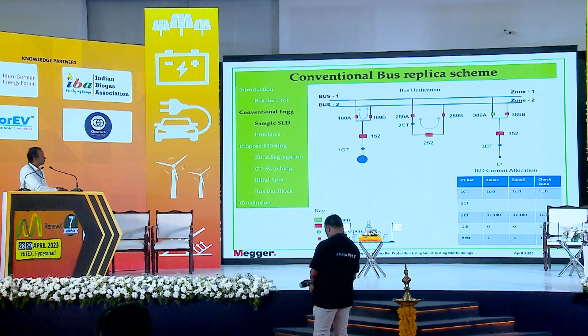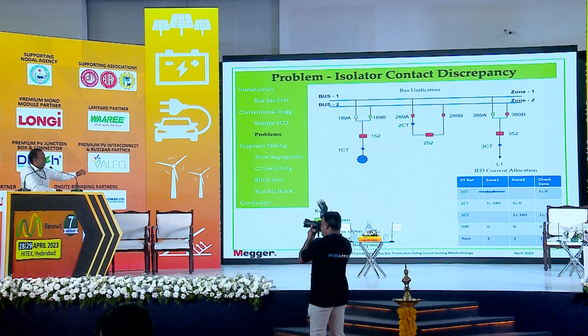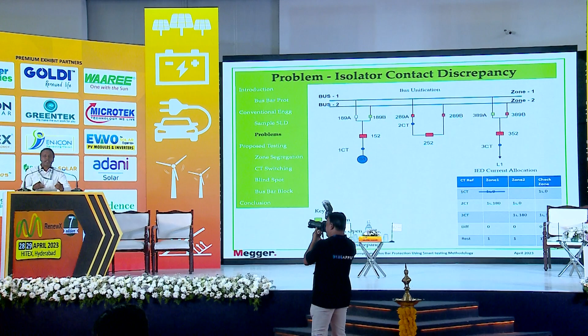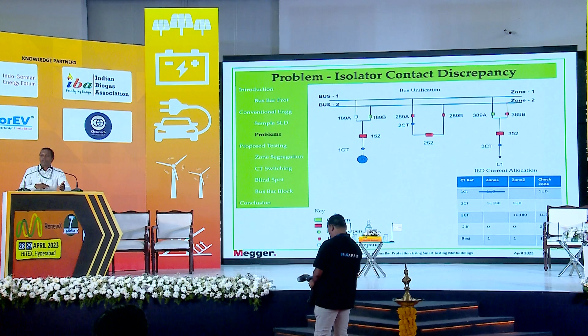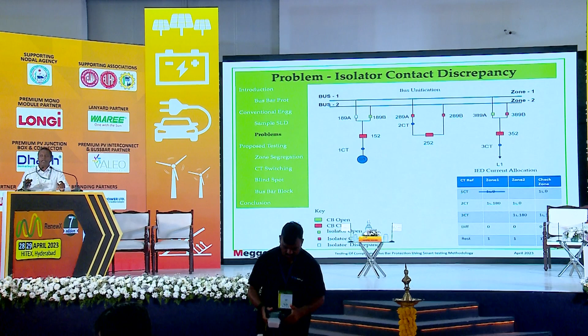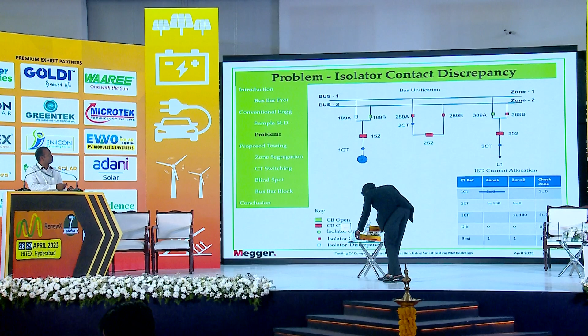And this is another example where an isolator is maloperated. You can see here the 89A is red color, but it is not giving the signal to the relay. The relay is not able to get the information because there can be a cable problem, there can be a loose connection which happens over a period of time. So when there is wrong information, what happens? This current which you see here will not be read by the relay. So when the current is missing, since an isolator maloperated, we cannot trip the bus. So after integrating the entire solar system to the grid, when an isolator is maloperating, the entire grid will be isolated from the solar system. So that will be another challenge. So how do we address all these things?